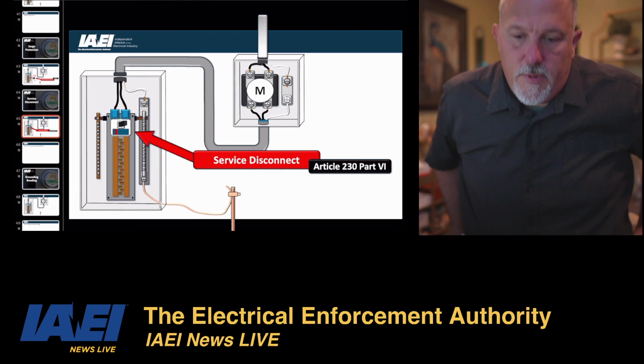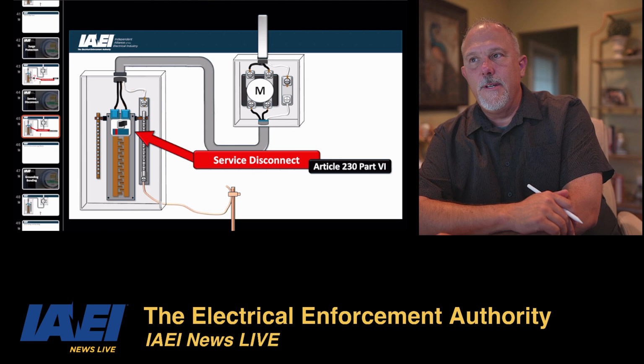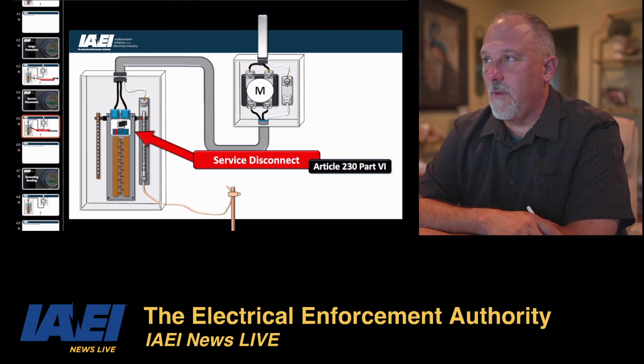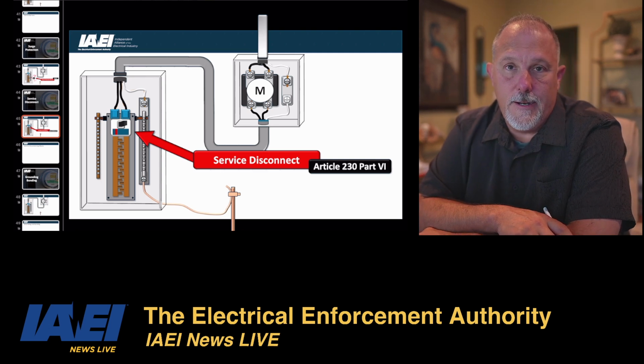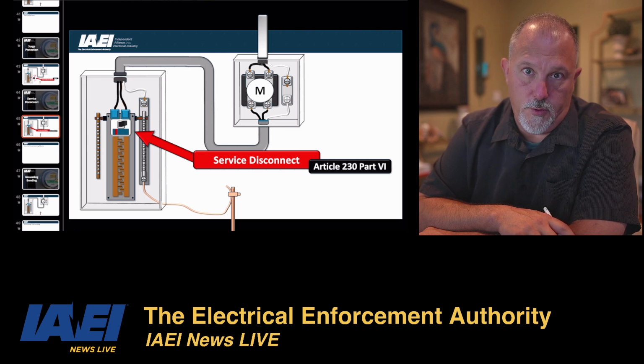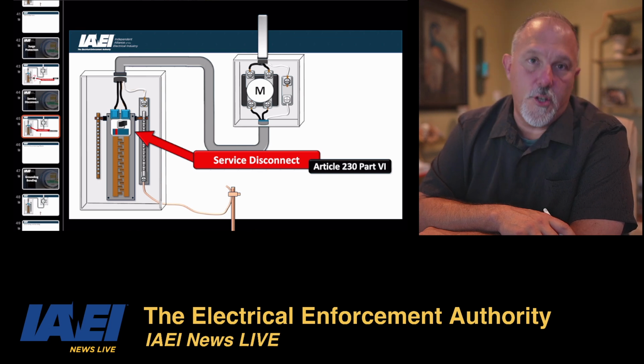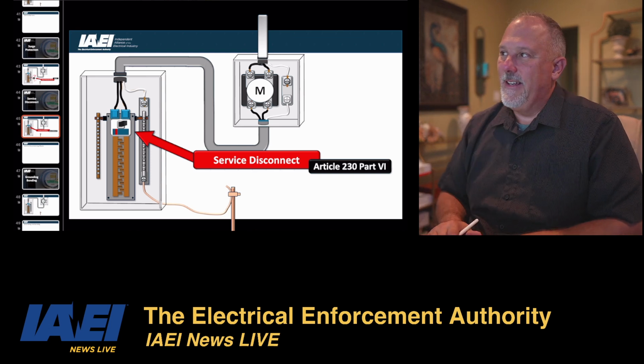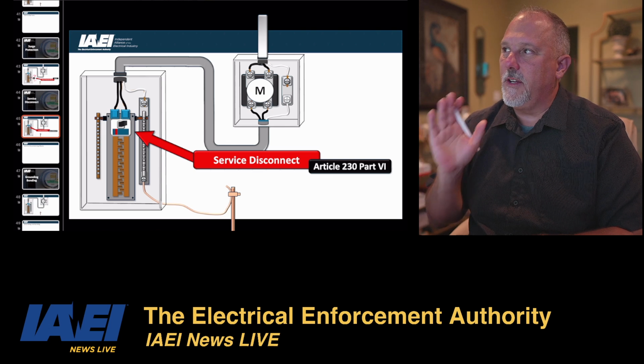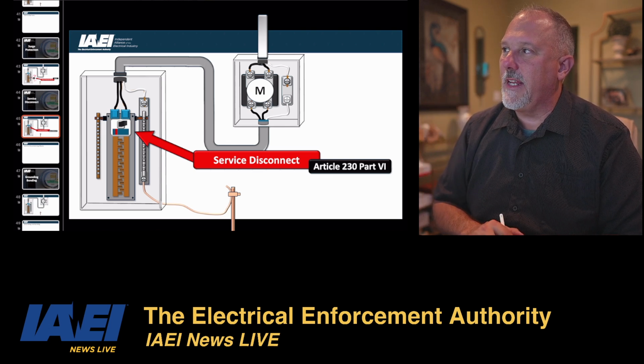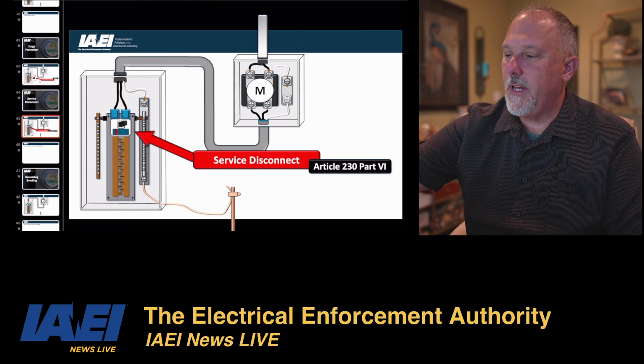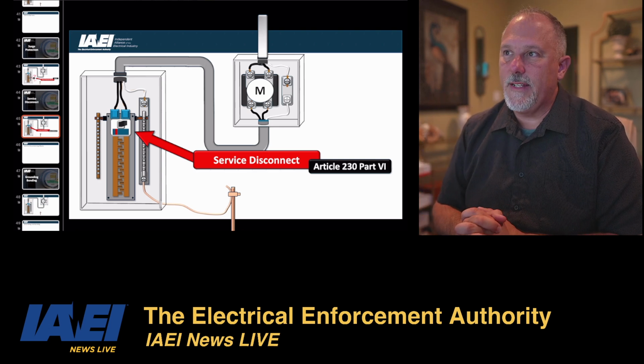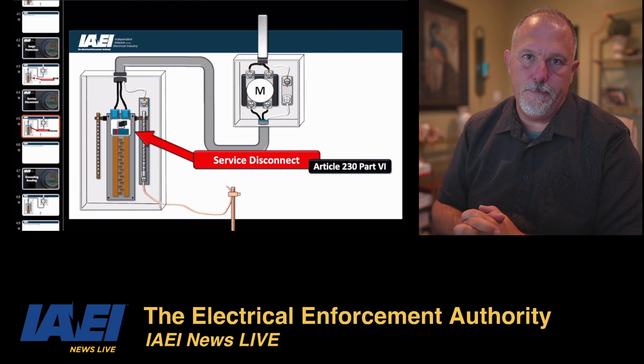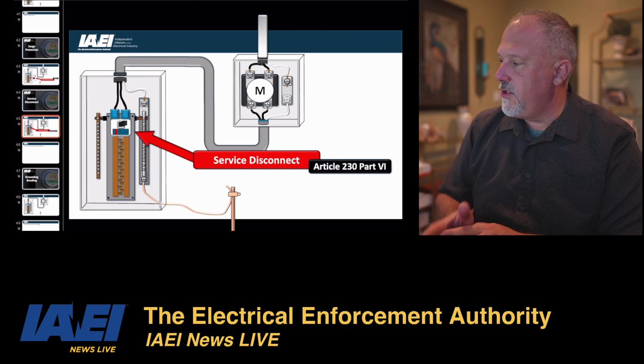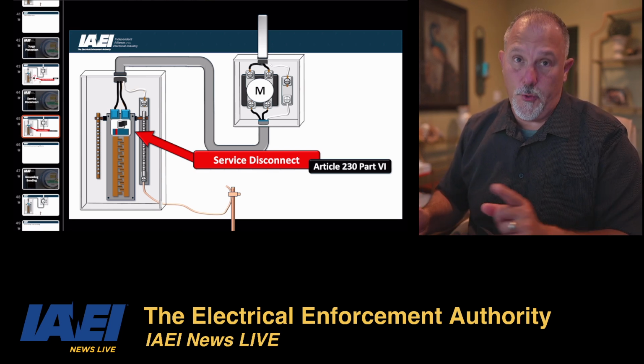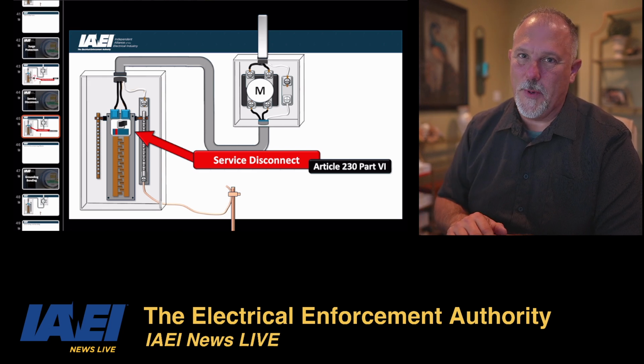So I talked to a few people, and I looked at the standard. I can make equipment 1,000 volts or less. I can make a dwelling unit panel board and mark it suitable only for use as service equipment. So arguably, you got to be careful how you read this, because the way I read it was if it's being marked as suitable for use as service equipment, then that sort of implies that it is convertible. But the way this is intended to be read is that if you have equipment that is suitable only for use as service equipment, it too is suitable for use as service equipment.